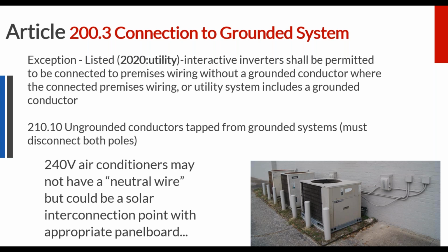If that circuit between the air conditioner and the service panel is dedicated, if there's no other load on that circuit, right now it's a branch circuit for the air conditioner unit. If you intercept it and put a power distribution panel there, it's now a feeder from the distribution panel to the main panel, and then your solar array plugs into the panel and your air conditioner unit plugs into the panel.